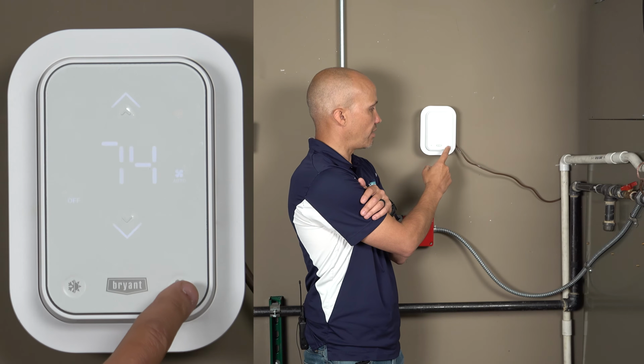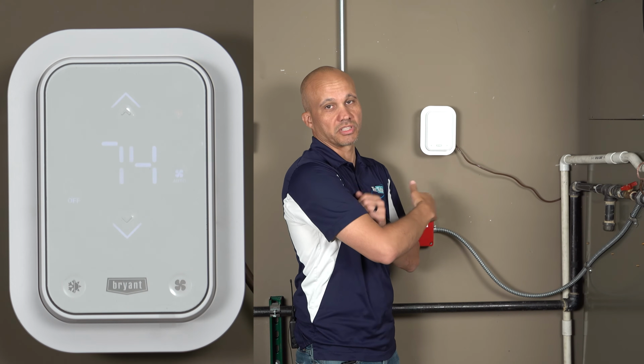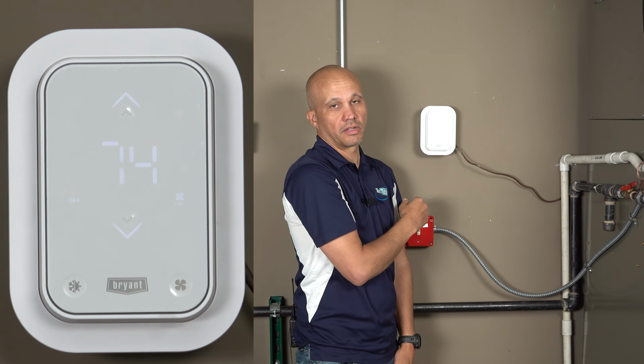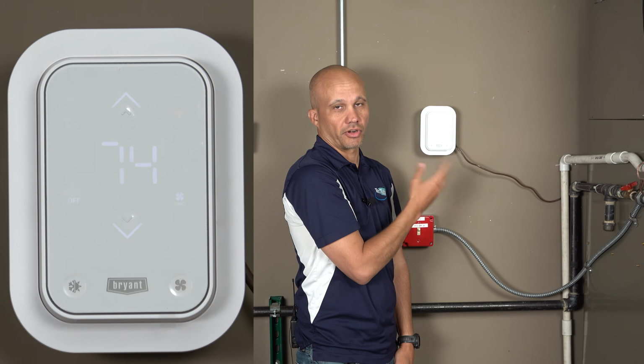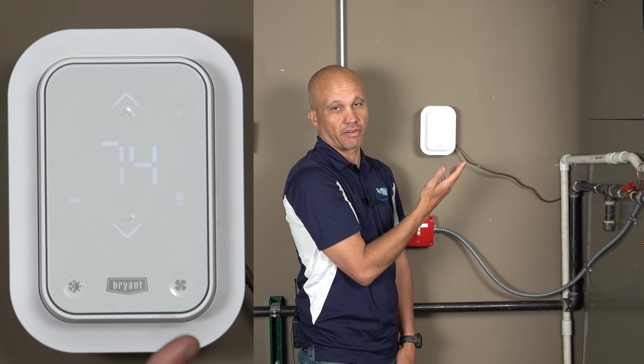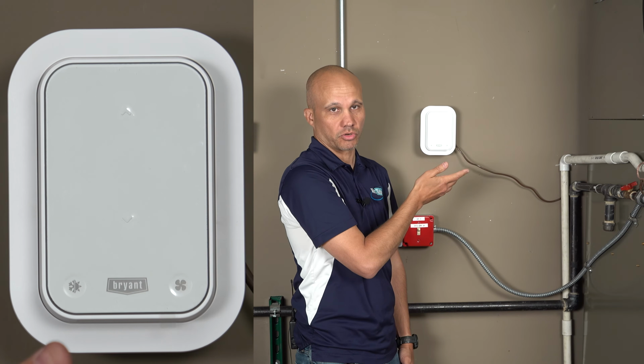The last button on the right here is the fan button. There's 3 scenarios there. There's auto, which means the fan turns on during a heating or cooling call. There is the circ button, which means the fan runs 33% of each hour. So it runs 20 minutes out of every hour. And if there's any runtime that's associated with heating and cooling, that counts towards the 20 minutes.